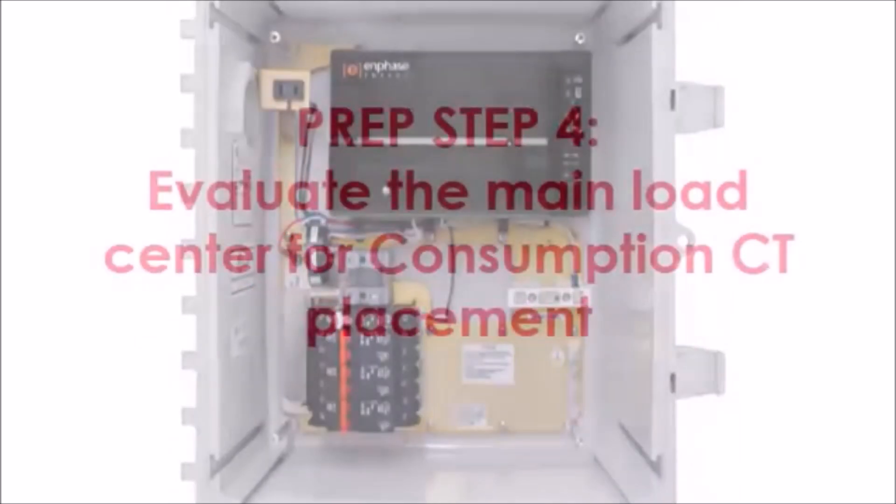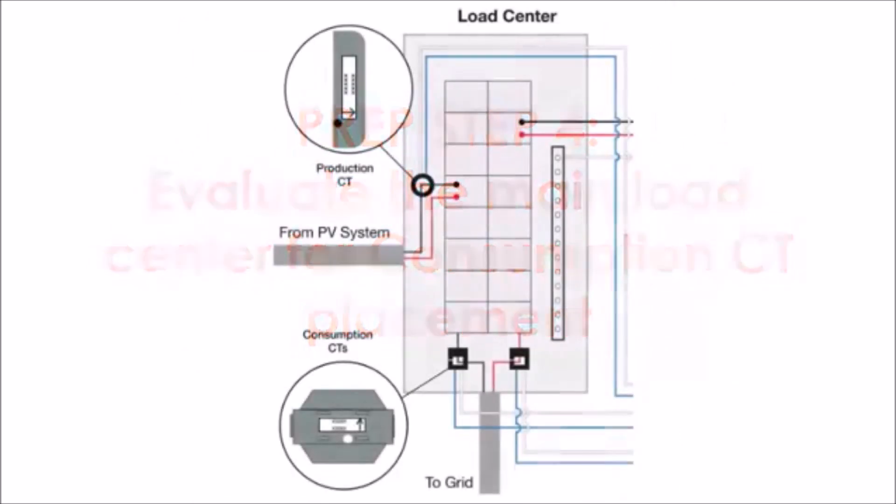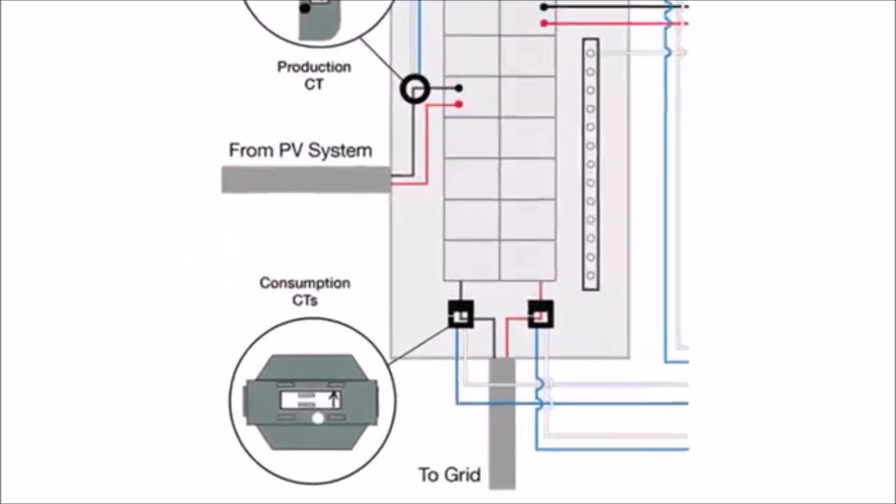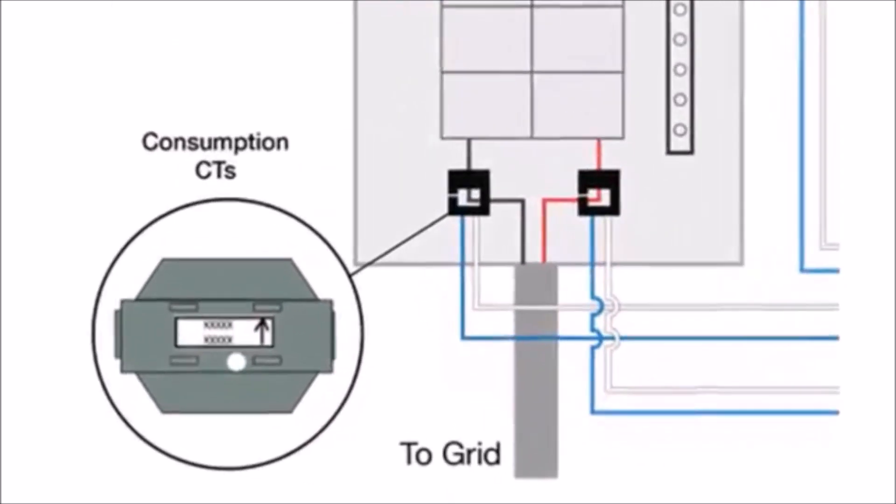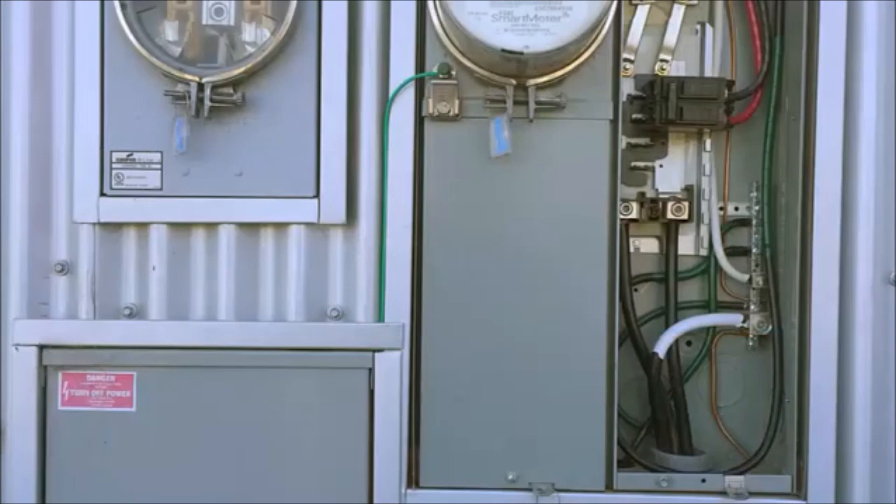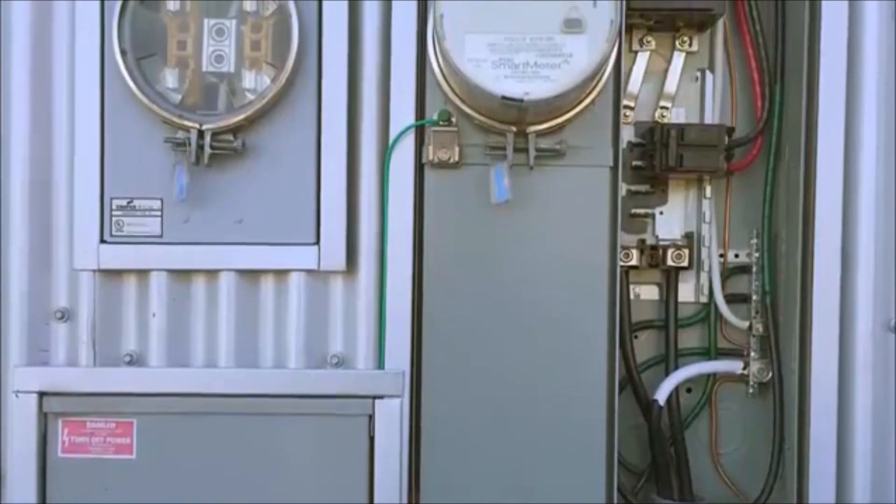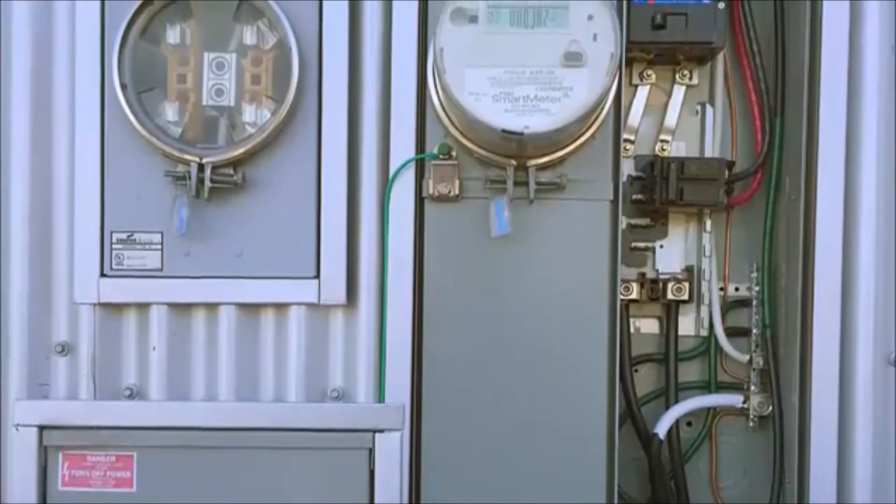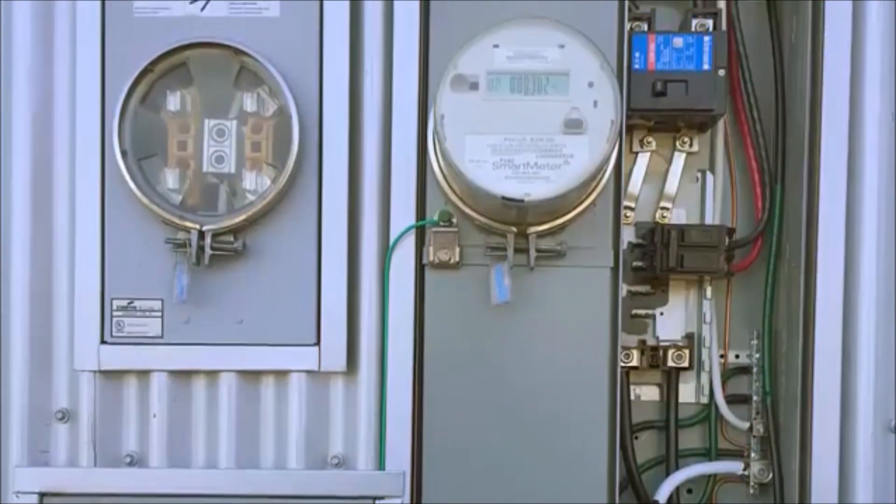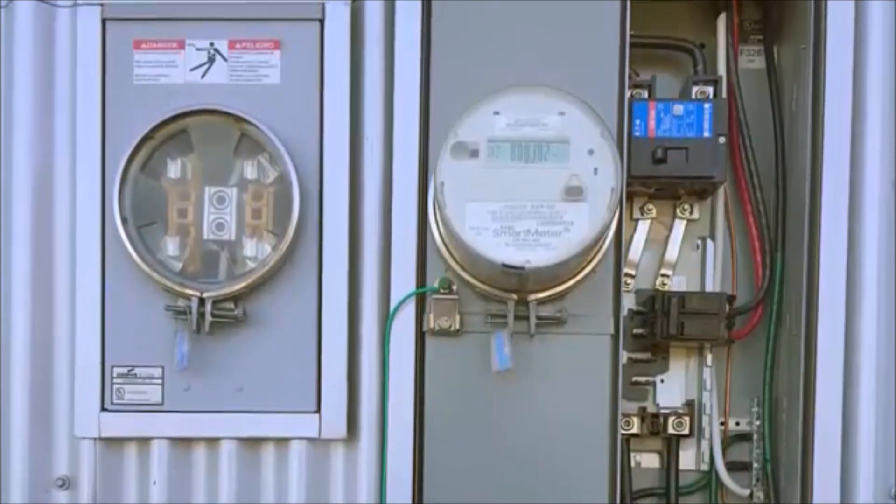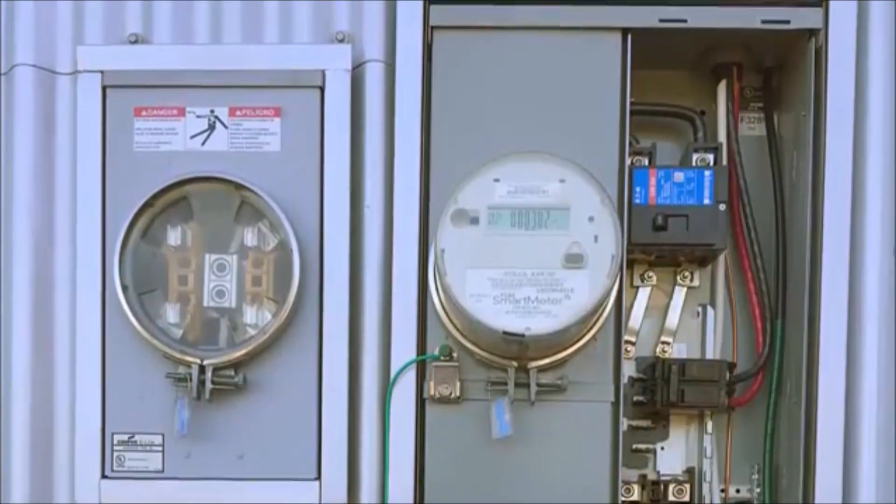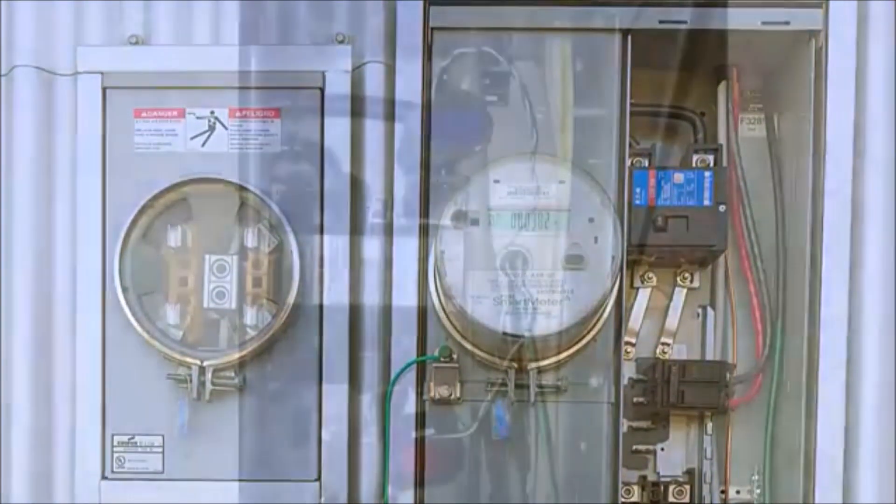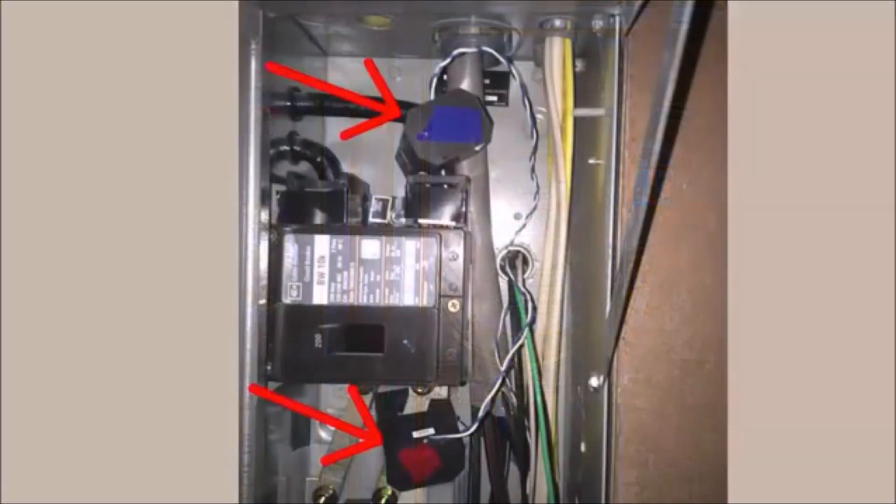Step 4: Evaluate the main load center for consumption CT placement. Before installing consumption CTs, evaluate the main service panel to determine if the split-core consumption CTs can be installed around the service conductors or bus bars. If the utility meter is installed in an enclosure separate from the main electrical service panel, the CTs can likely be installed without rewiring the service equipment. Here are some examples of consumption CT installations.